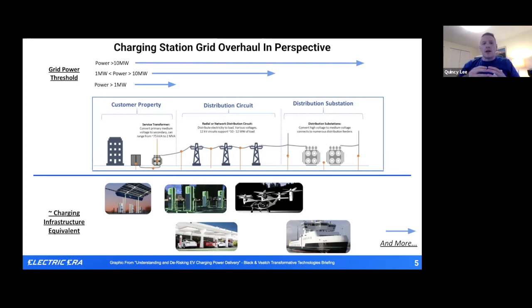Importantly, on the top part of the page you can see the grid power threshold levels, where different charging station power levels start to interface and require overhaul of various parts of this circuitry stack. For smaller stations, like an EVgo, you're looking at less than a megawatt of power. You're only really making alterations to the customer property, things like your local transformer, primary conductor, maybe your medium voltage distribution panel, and certainly a lot of conduit and trenching.